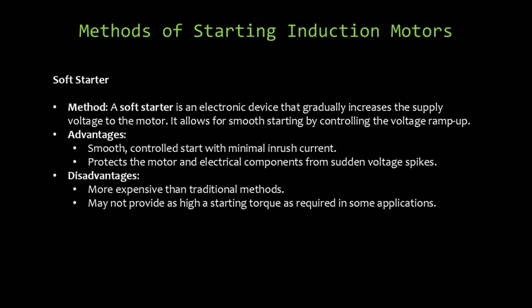Soft starters represent an electronic solution to motor starting challenges. This device gradually increases the supply voltage to the motor, allowing for a smooth, controlled start. By managing the voltage ramp-up, soft starters minimize inrush current and protect electrical components from sudden voltage spikes. While more expensive than traditional methods, they offer superior control and protection for motor systems.